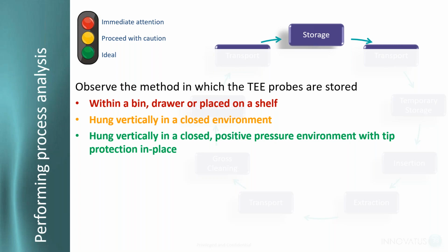Hung vertically in a closed environment, better, but ideal: hung vertically in a closed, positive pressure environment with a tip protector in place. There are some storage cabinets out there. There's actually one I looked at about 6 months ago, and the customer thought they were doing a great job. They were hanging the probe vertically in this cabinet, but they kept damaging their tips on their probes, and I couldn't figure out why. So I went and visited them, and as I was following the probe around, I saw one hanging in a cabinet, and I examined the cabinet, and they used these toggle bolts to fasten the cabinet to the walls, and the threads from the toggle bolts were sticking into the cabinet right at the tip level, and the tips did not have tip protectors. And so they were banging the tips of these probes up against the bolts that were used to mount this protective cabinet. So it was kind of a good news, bad news thing.